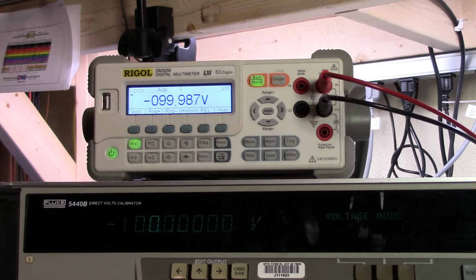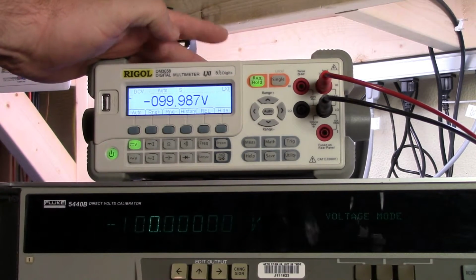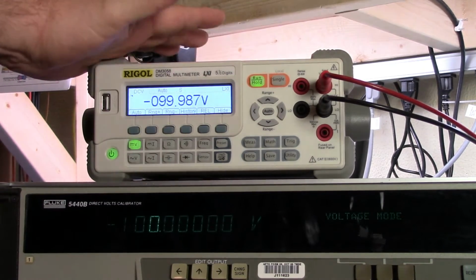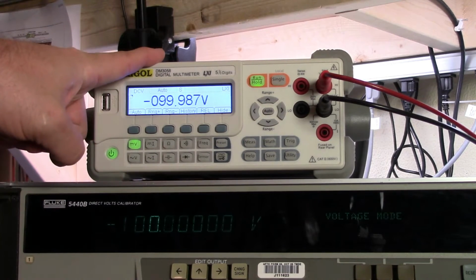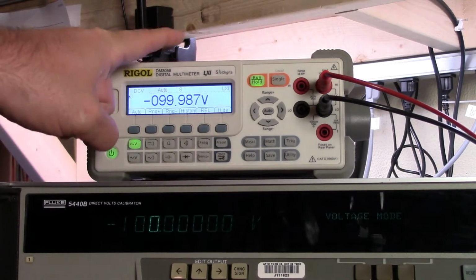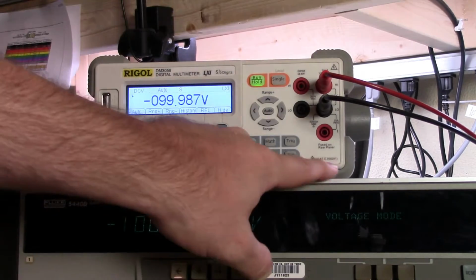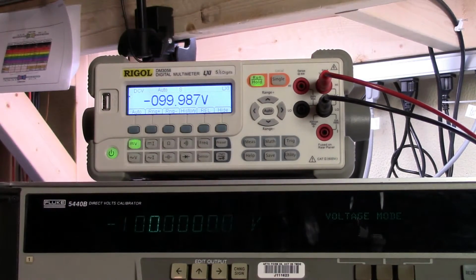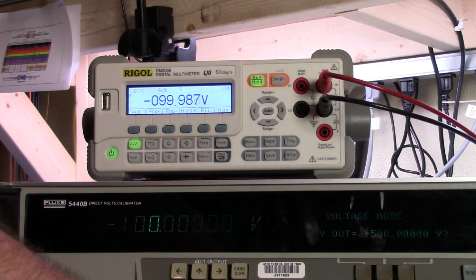Let me pause, because one of the things that you should always check before you go to high voltages is whether your multimeter can do it. Now I think I'm good on this up to 600 or 500 volts, so I want to just check and make sure what my upper limit is before I set it too high. Okay, so the limit does say that it's good to 500 to 1000 volts, so let's take it to 500 volts.